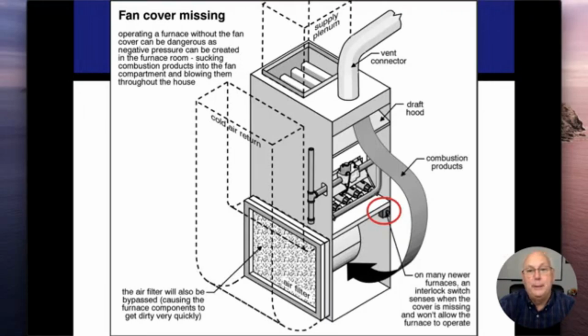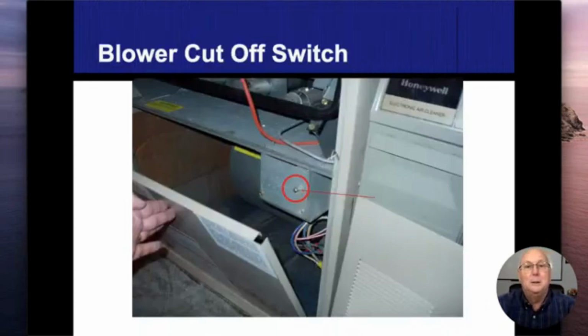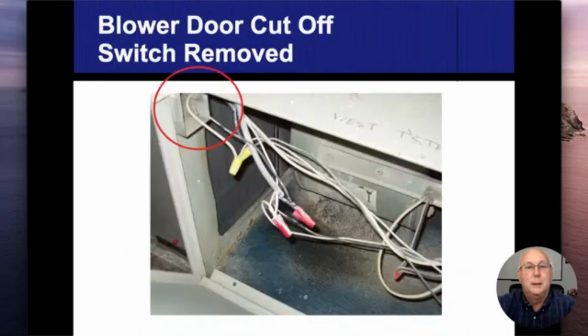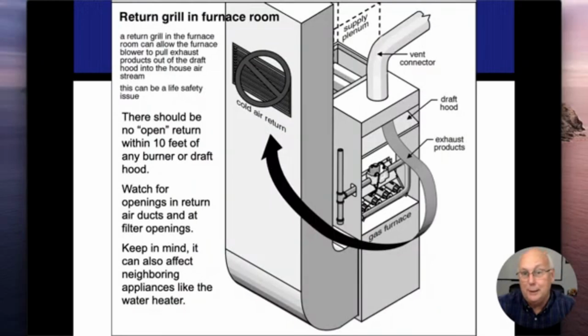Having these things operate and depressurize a room does happen. It is rare. This is mostly going to be a problem on a natural draft furnace, not so much on a high efficiency or a mid efficiency furnace. But what we're talking about, and maybe the next slide will show this, here's the blower door switch on this one. This blower door switch was just bypassed, and I do this: I take that door off and make sure the furnace shuts down. Just because the switch is there doesn't necessarily mean it's not a problem.